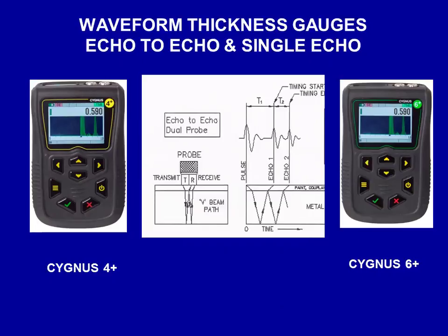So now you've got a gauge, we have it in the 4 Plus and the 6 Plus, that can do multiple echo, can do echo to echo, and can do single echo. The Cygnus 4 gauge also has an A-scan, which is now you can see what the sound is doing in the metal. We simplified it. I'm not saying you have to be a Level 2 in order to interpret it, and I can show you that as well. Or you can go and change it and use it more like a flaw detector, but it's not a flaw detector. Thickness gauges were only ever designed to support the use of a flaw detector. They were never ever designed to replace it. Okay, number one.